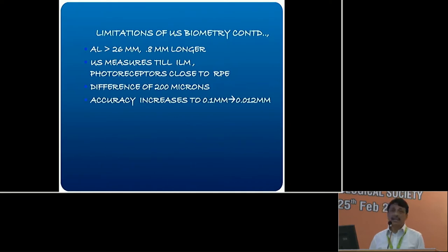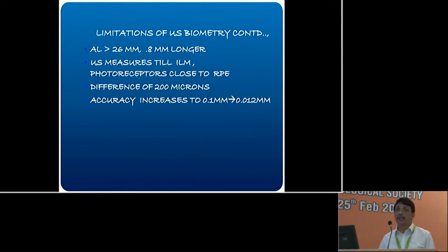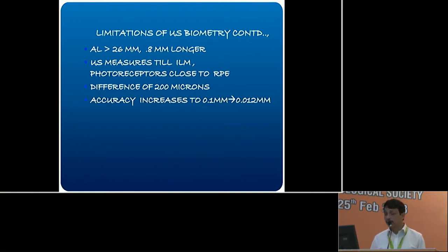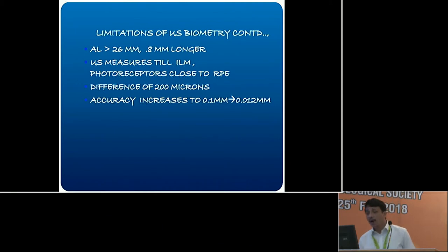The third difference is accuracy. Accuracy increases from 0.1 mm with ultrasound to about 0.012 mm with optical biometry, which is quite significant because of the shorter wavelengths. So those are three basic theoretical problems of ultrasound that optical biometry addresses.